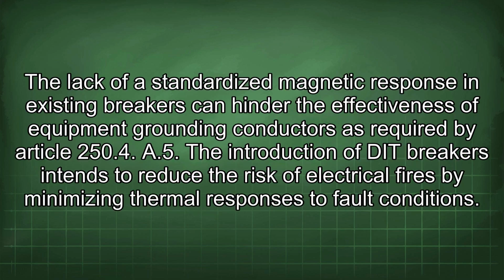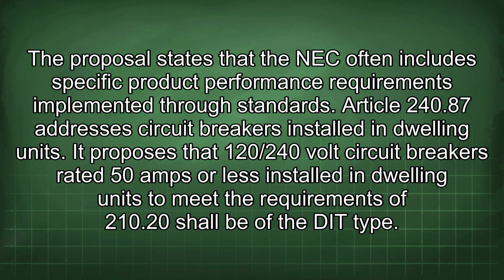The lack of a standardized magnetic response in existing breakers can hinder the effectiveness of equipment grounding conductors as required by Article 250.4(A)(5). The introduction of DIT breakers intends to reduce the risk of electrical fires by minimizing thermal responses to fault conditions. The proposal states that the NEC often includes specific product performance requirements implemented through standards.